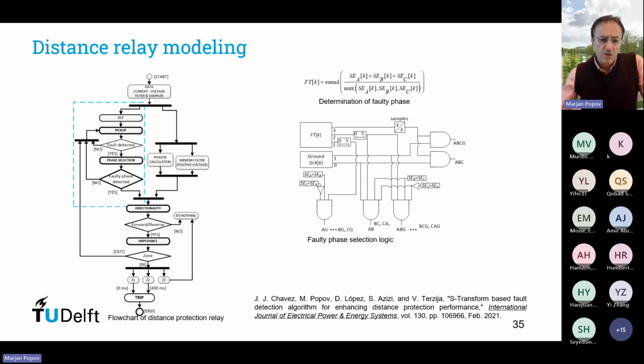After performing a lot of cases, simulations with hardware-in-the-loop simulation with commercial relays, we found out that with converter-based faults, IBR faults that I have mentioned previously, protection mostly experienced difficulties in case of ungrounded faults. Two-phase faults and three-phase faults, ungrounded faults.